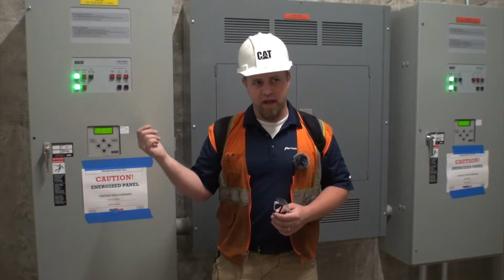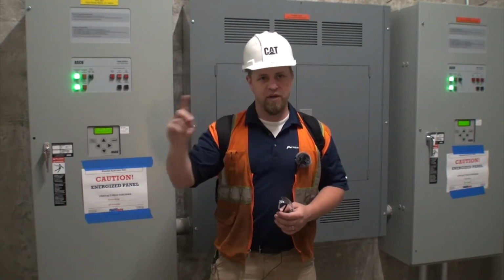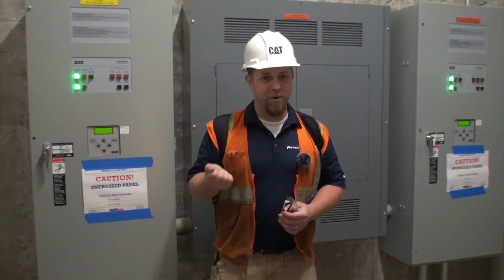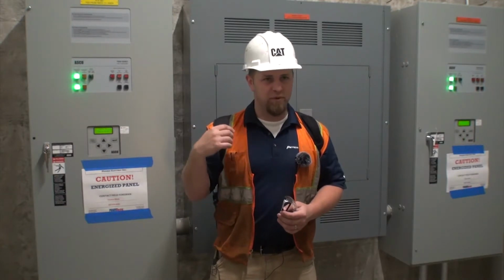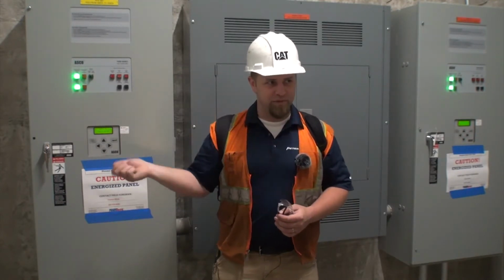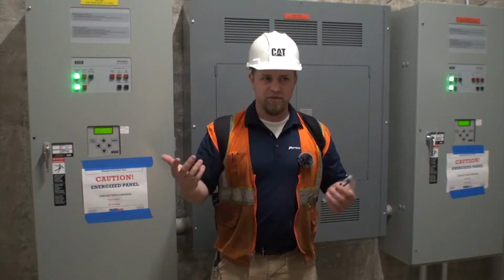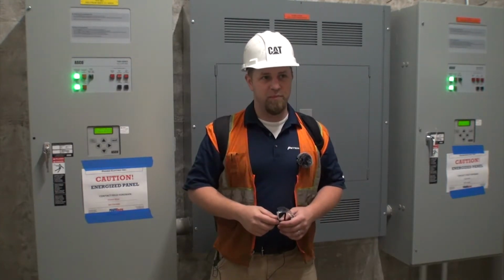With the monthlies, I do the same thing, but I go up there, check everything, make sure your breaker's on, because you're never going to send voltage. And if it's not in auto, when you flip your switch, it's not going to start. So that's where the ABCs come in and really play.